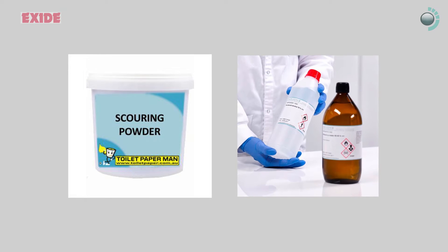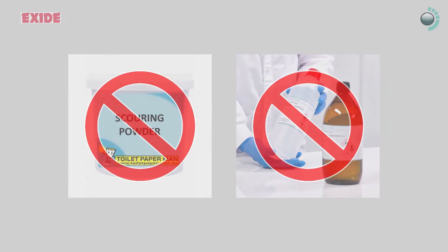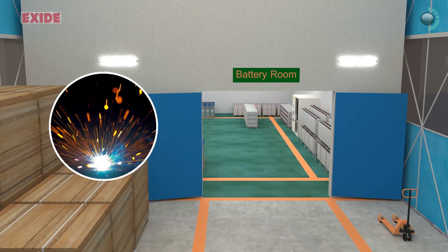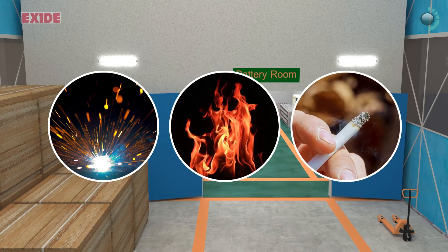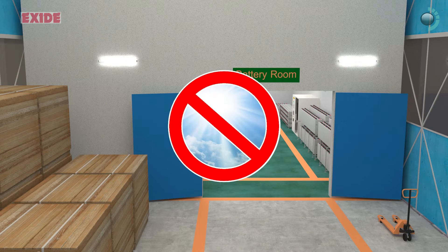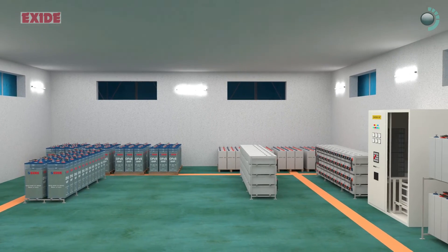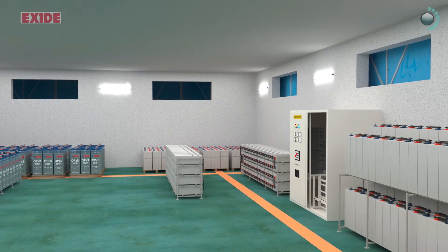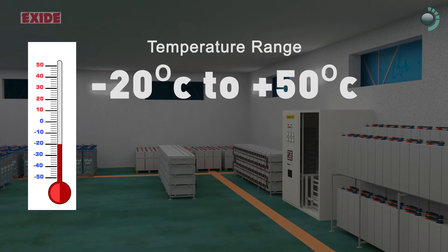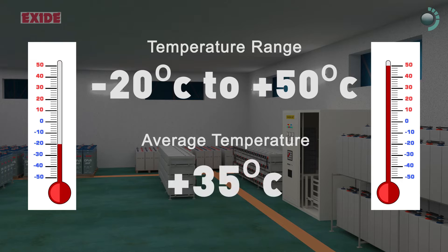Don't use scouring powders and solvents for cleaning lids as it can damage the plastic surface. Keep sparks, flames and lighted cigarettes away from battery room. Always avoid direct sunlight, but ensure well-lit battery room along with adequate ventilation at all times. Ensure ambient temperature range of minus 20 degrees to 50 degrees centigrade, maintaining an average of 35 degrees centigrade.